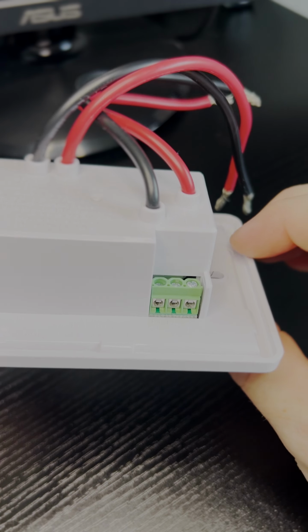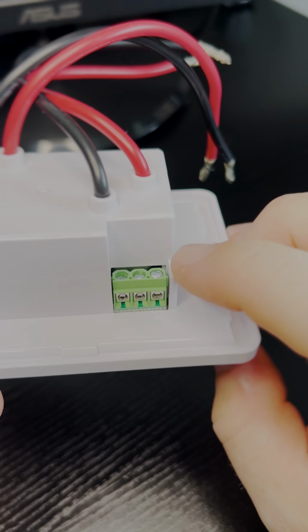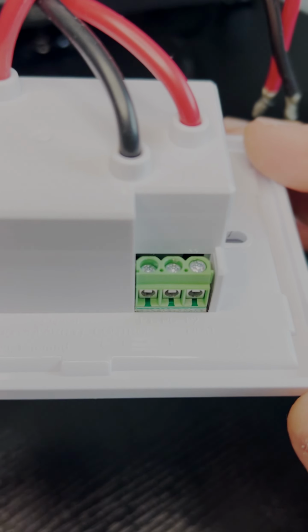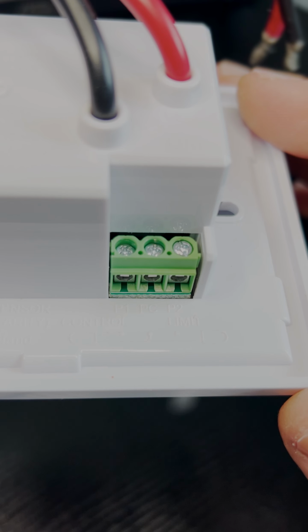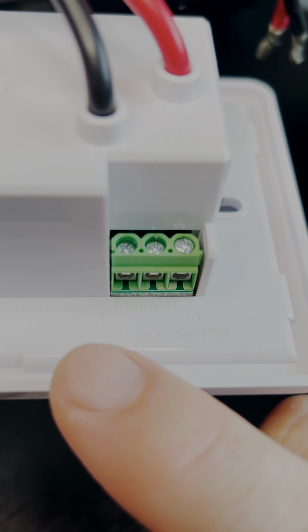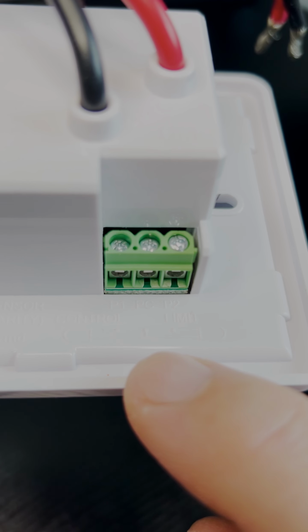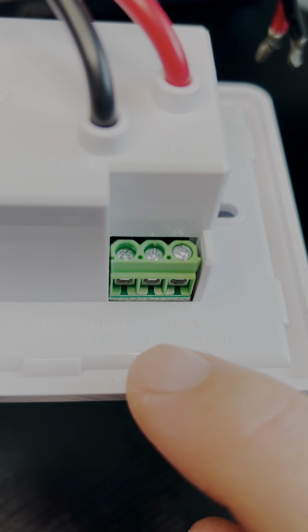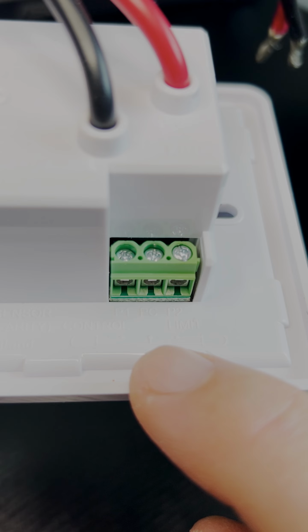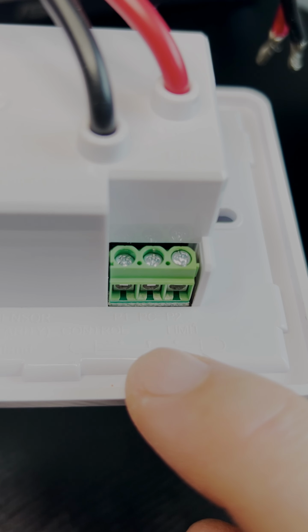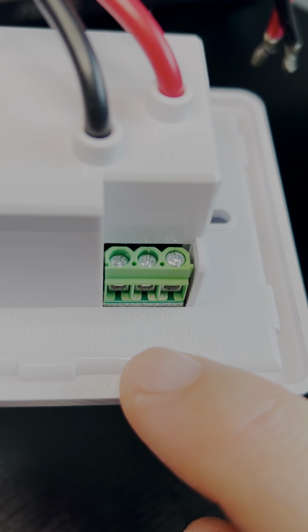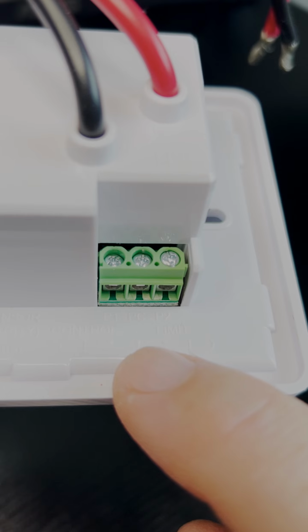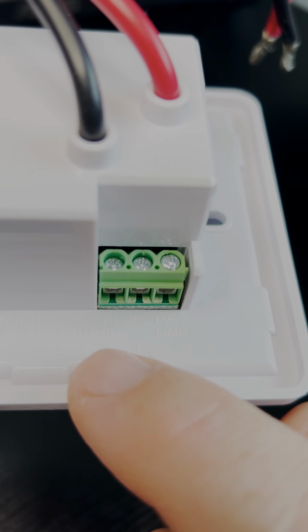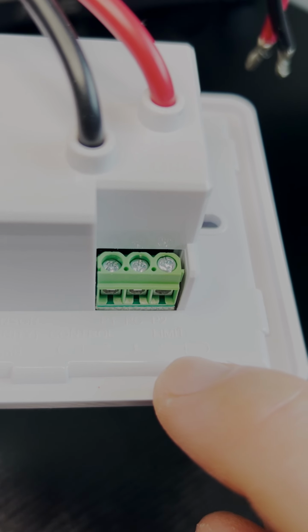Looking at the back of the StrataHeat thermostat, you'll notice three little terminals on the side. If you look closely, each one is labeled either for control or limit, and there's also a center terminal. That center terminal is actually the common power, and it will always need to be connected with one lead of the probe, the other lead going into either the P1 control or P2 limit.